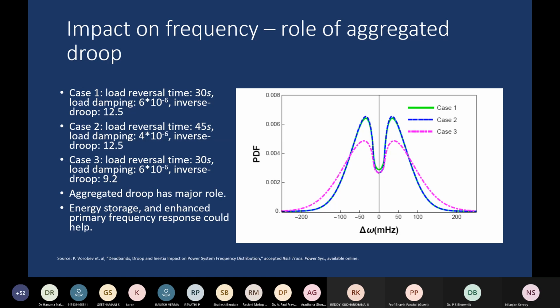So when you look at the load for the power system, every system has a certain load reversal time, which means that the load shows gradual variations, and this load reversal time is generally about 30 seconds to 1 minute, maybe 5 minutes. In industrialized societies, the load is very, very steady because of the high level of industrial load. While in a society like ours, where the load is primarily agricultural and domestic, the load fluctuates very fast. So the load reversal time is much less. This kind of study was done for different load reversal times, and it is seen that the load reversal time has a significant impact on the PDF of the ambient frequency.